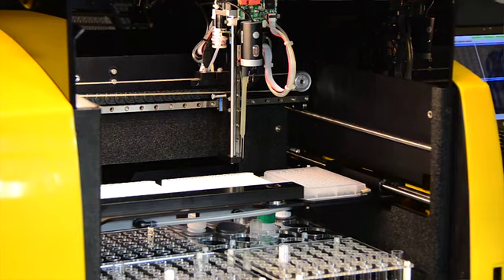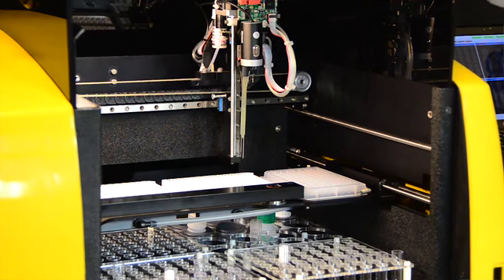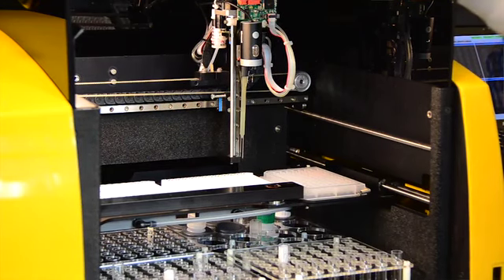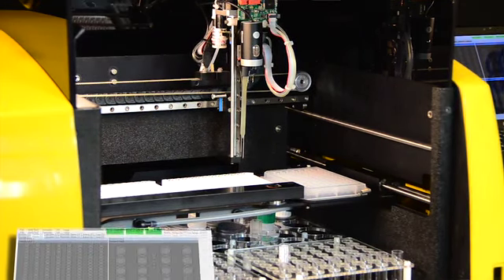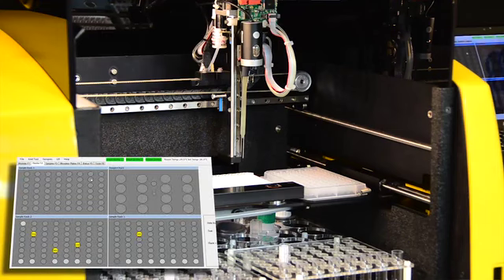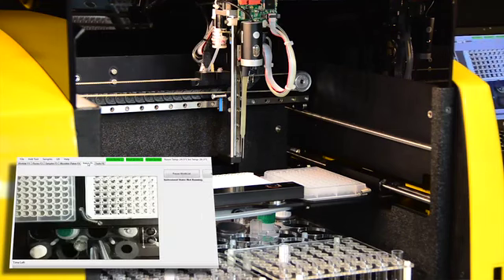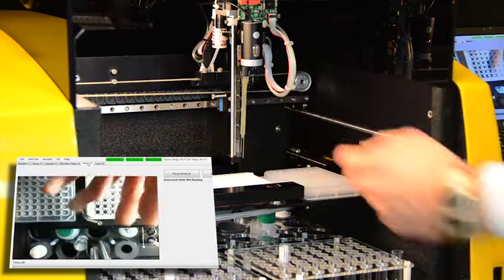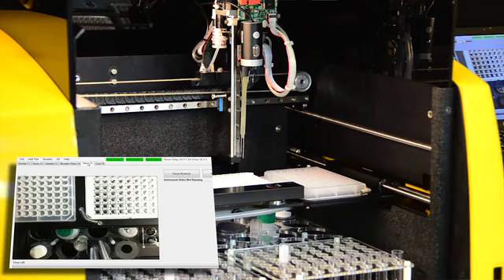Also on the probe assembly, you will see the camera right on the front. That camera is a really unique feature that we use to remotely diagnose any problems that are going on in the instrument. So we can log in and see what's going on both on your computer, on the software, as well as what's going on the inside of the instrument by looking on the status tab and watching what the camera is doing. As you can see, the camera is a live feed right there.